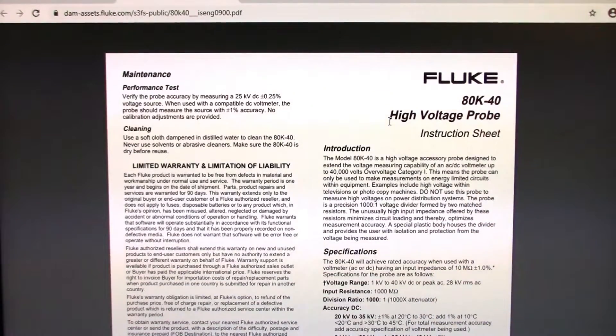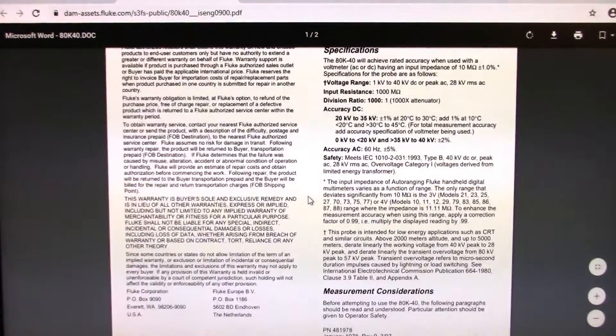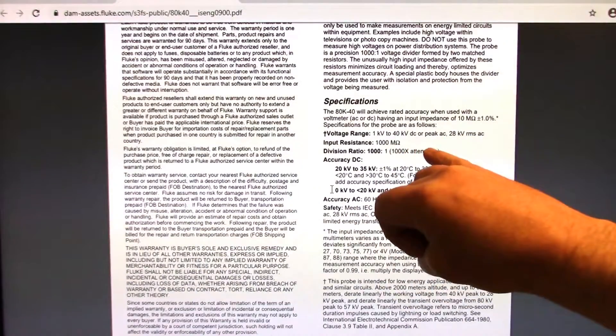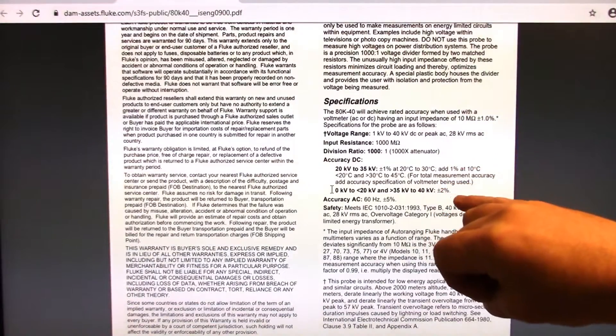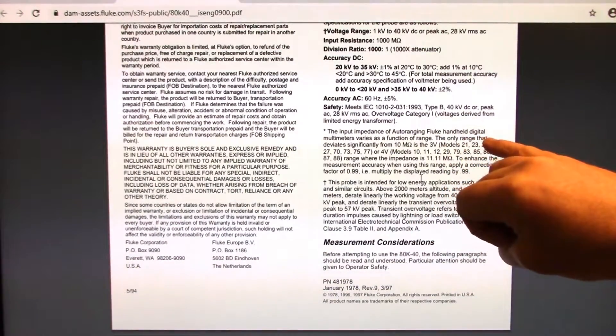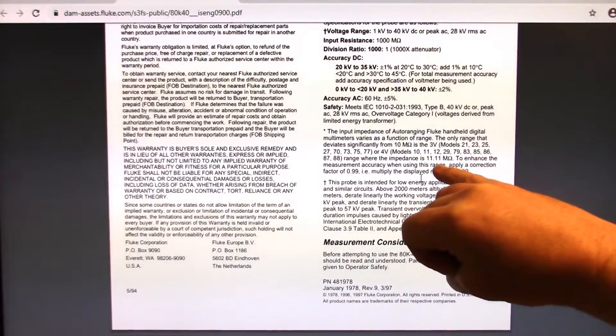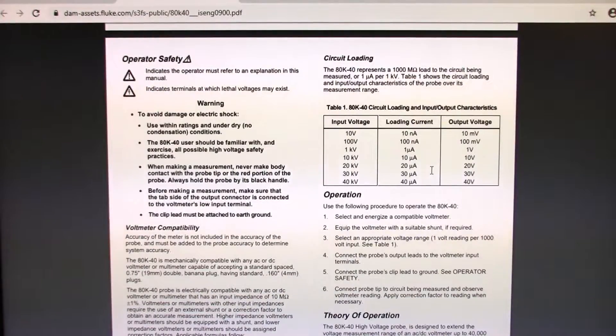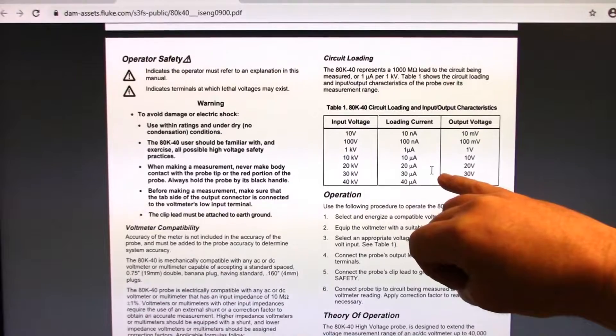Even better is the Fluke 80K40 instruction manual. I'm going to link to this below in the description because this is a pretty good manual, better than the one that comes with these things. As you can see, it's got the exact same specifications. 40 kV DC, 28 kV AC input resistance, 1000 mega ohms. It's going over the impedance of the auto ranging in the Flukes. A lot of Flukes have actually got an 11.11 mega ohm internal resistance and we're going to check that out. Even in different scales, it will change. They just say if you've got that, you can just multiply your voltage by 0.99.